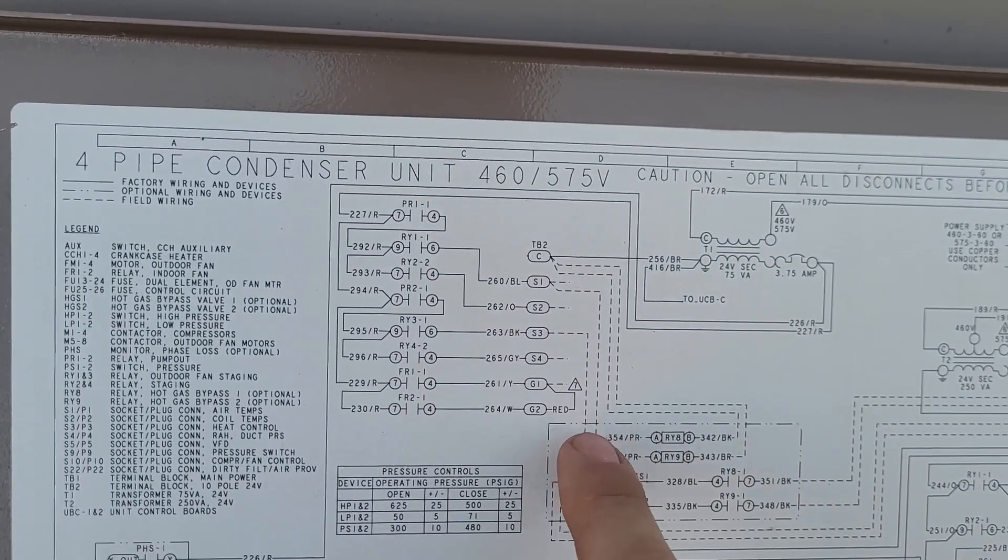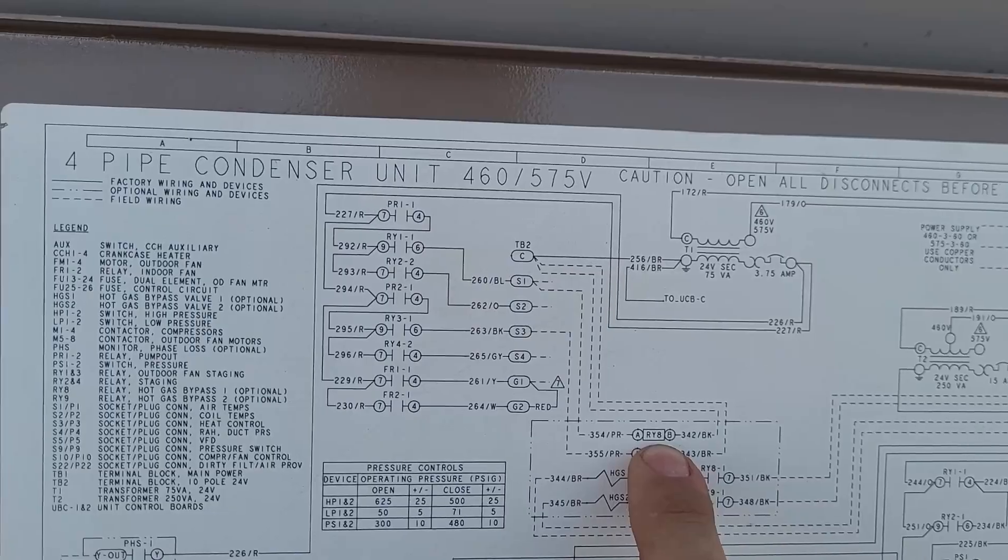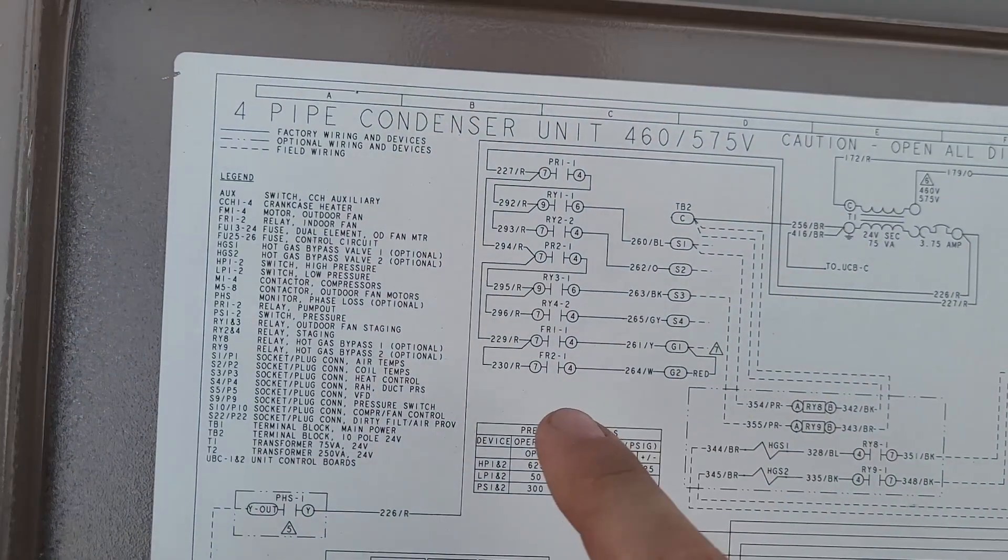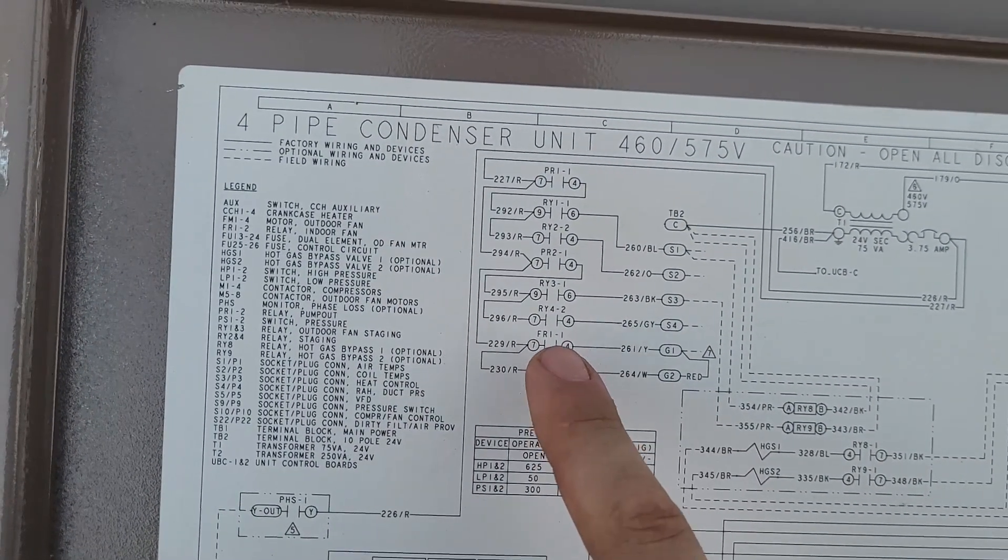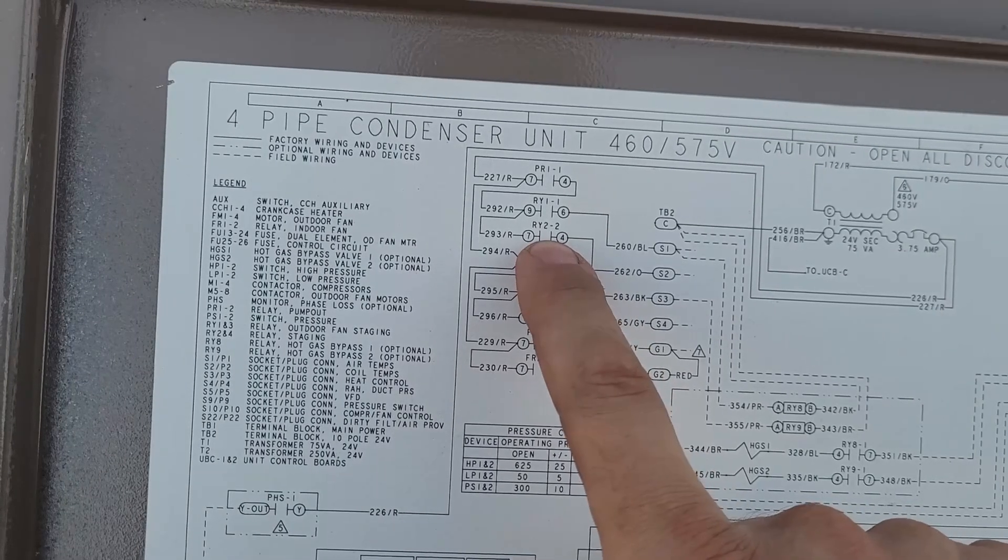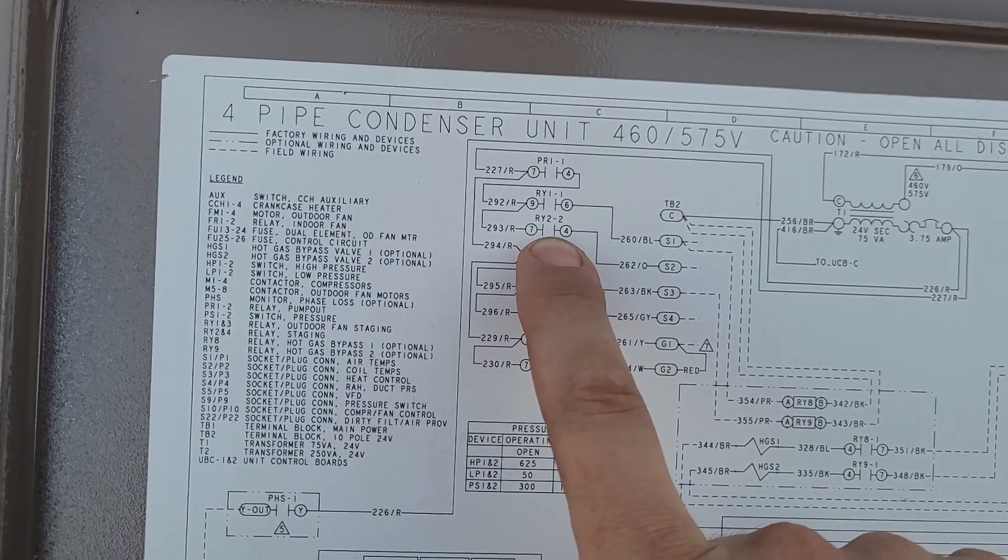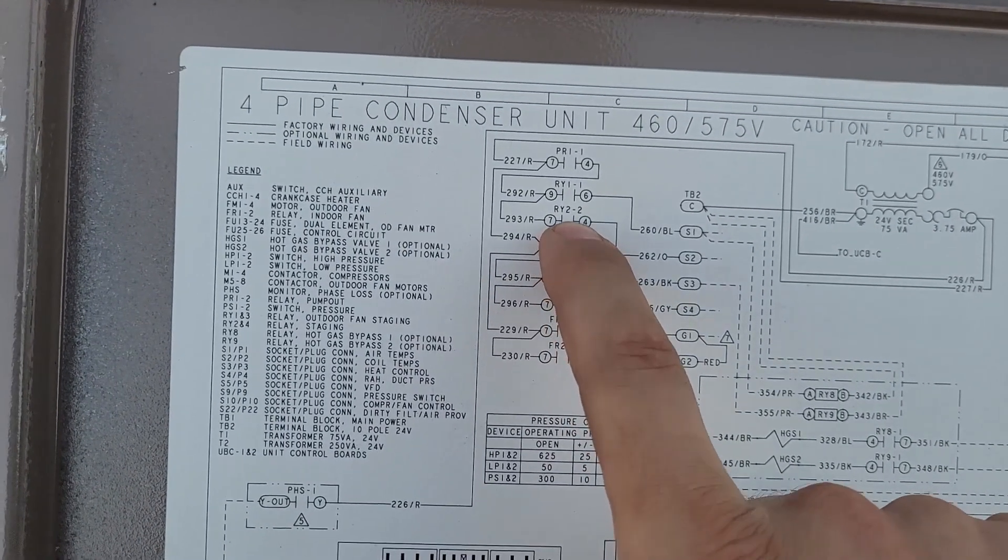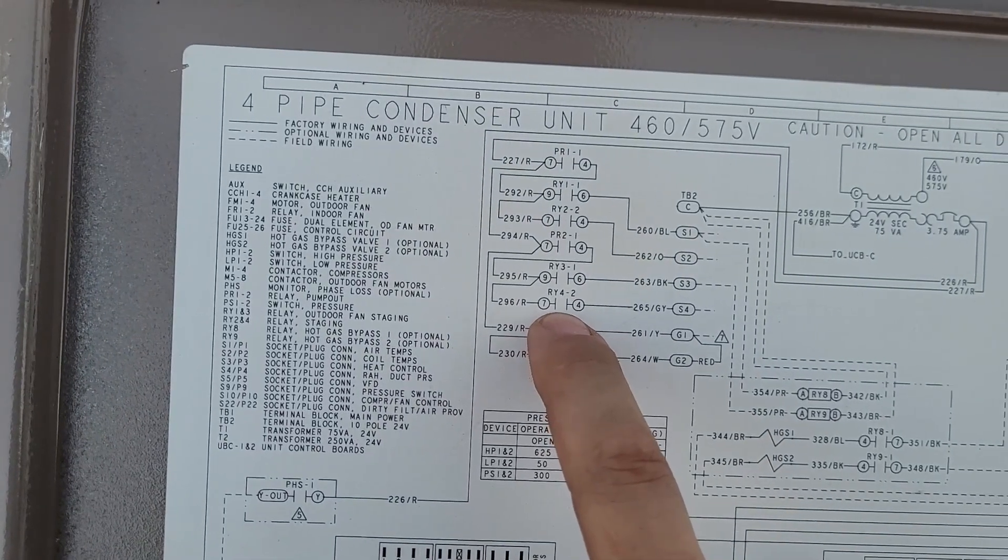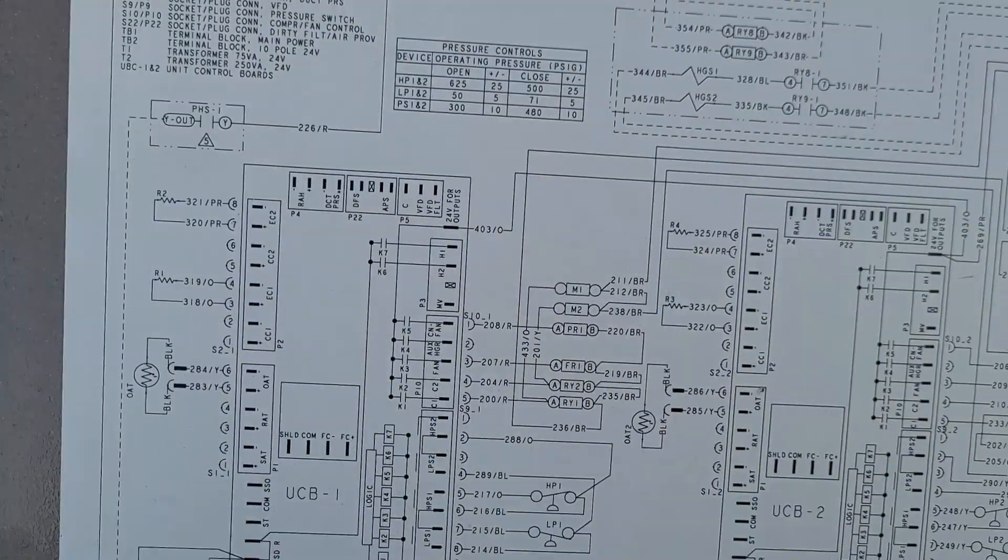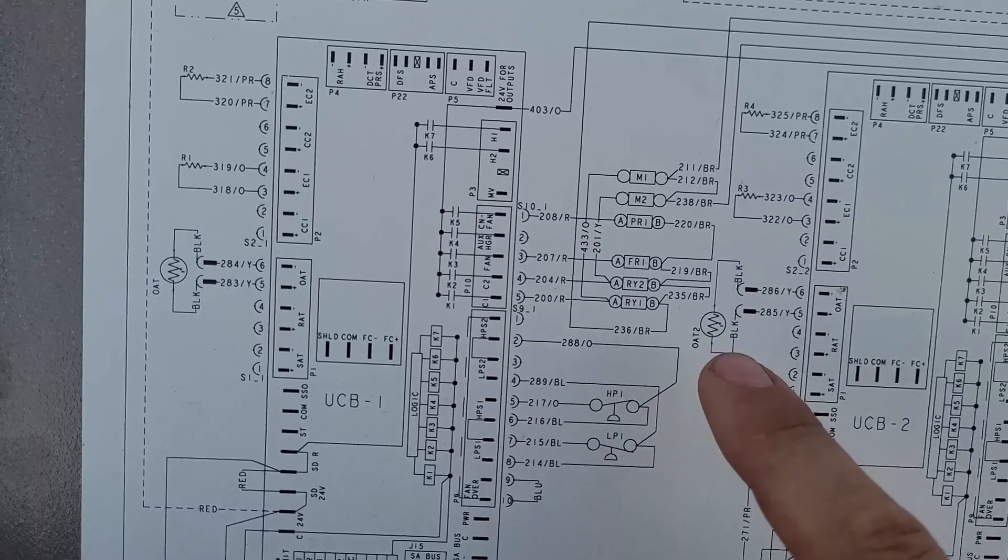It also can come down here and do hot gas bypass. You've also got dry contacts on RY2, which is basically the compressor relay, and RY4, which I think, again, is a compressor relay.